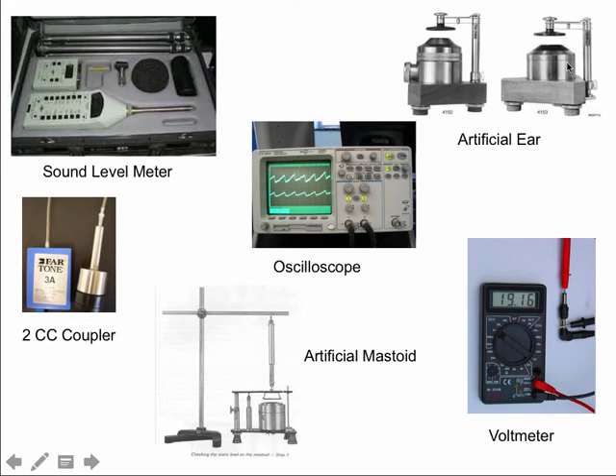This is an illustration of an artificial ear. It's also known as a 6cc coupler. As a coupler, it serves as the bridge between the sound level meter and the headphones of the audiometer. When you're doing insert earphone calibration, the coupler is actually a little more simple, and it's known as a 2cc coupler, and it looks like that. With one end connected to the microphone of the sound level meter and the other end connected to the tubing of the insert earphone. Here you've got an artificial mastoid.